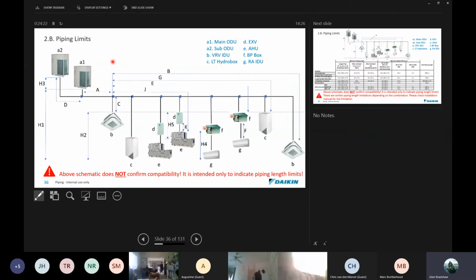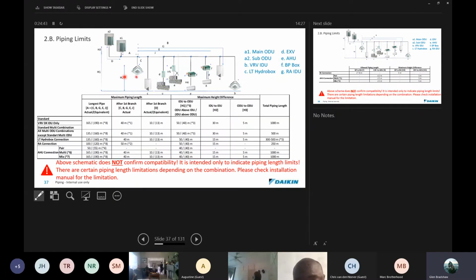because when we start going past those limits, we may have to upsize piping, and in some instances you may actually overshoot the total allowed piping length completely. Okay, so we need to make sure you don't go into those. So like I said, this is a schematic purely to show you what the indicated pipe lengths are, what the limitations are. Okay, so here that schematic is again, and so we have an actual and maximum.